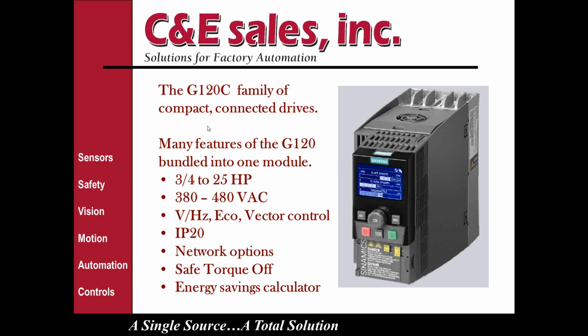So you order a particular part number and it comes with the controller and the power module matched up as one unit. It makes it very simple to do replacements if necessary. It's a little bit more compact in size, so it can save a little bit of panel space, not a great deal, but some. They're available in 3/4 to 25 horsepower in the 380 volt to 480 volt range.